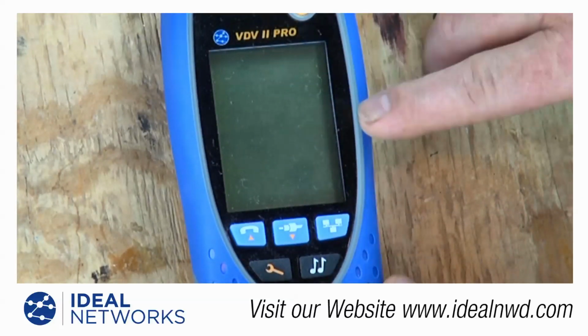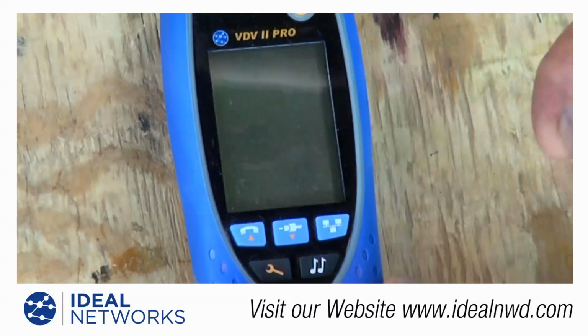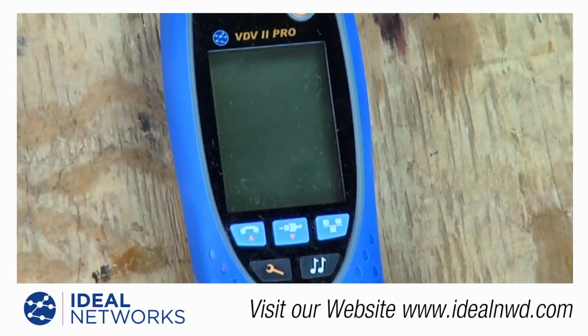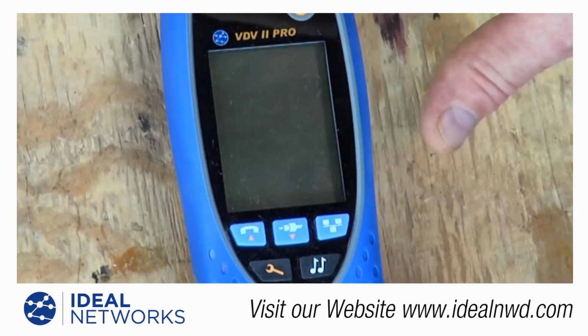Measuring length with the VDV Pro can be done using the built-in time domain reflectometer, or TDR. A few things you should know about a TDR: they're only as good as what you tell them to do. All cables have a known nominal velocity of propagation, and if we know that, we can set the TDR to that percent, which is basically the amount of time it takes electrons to travel down a cable—some percentage of the speed of light.